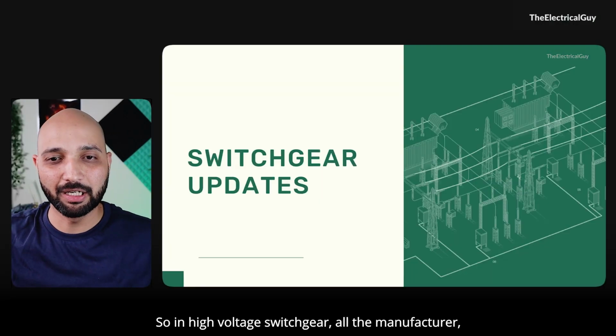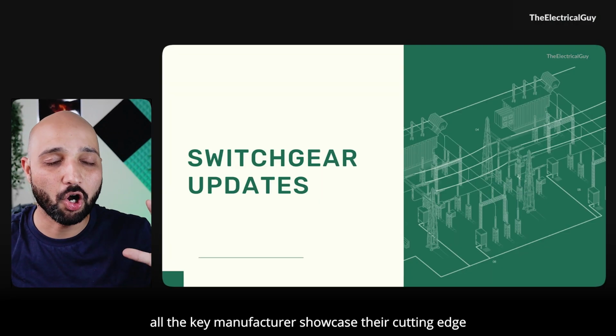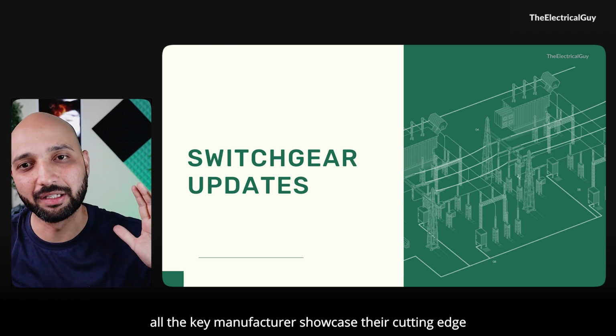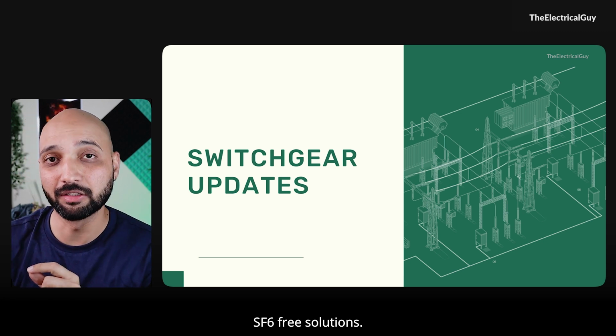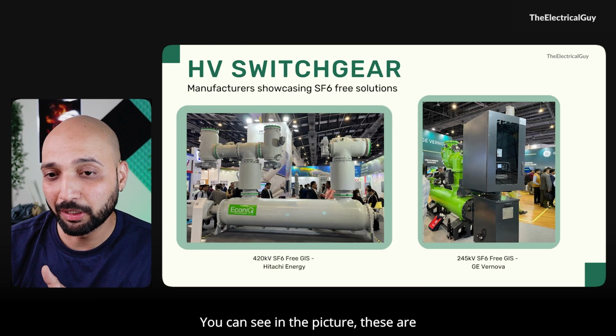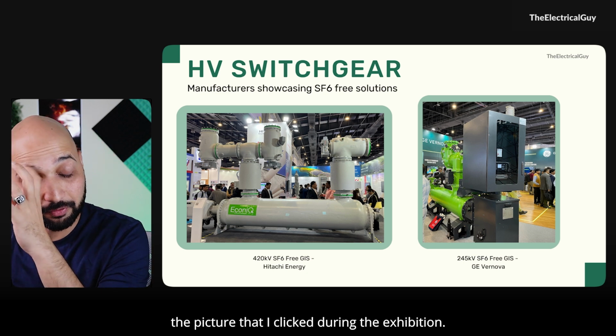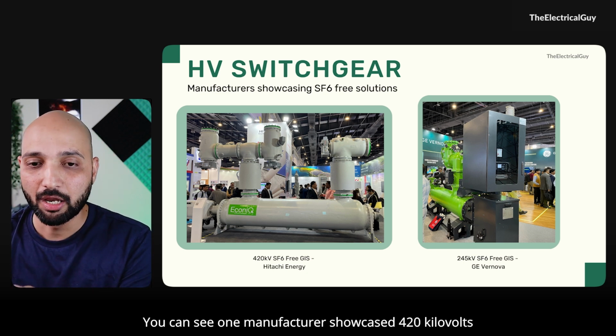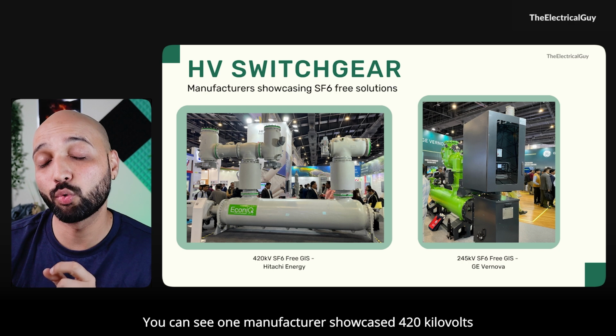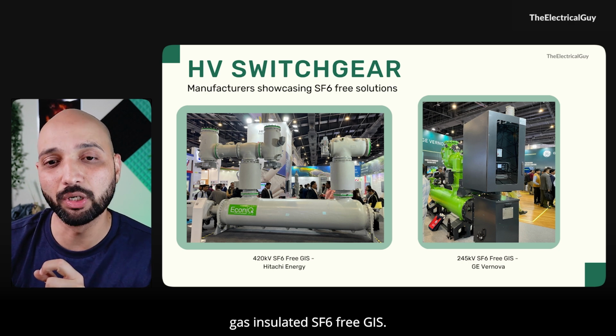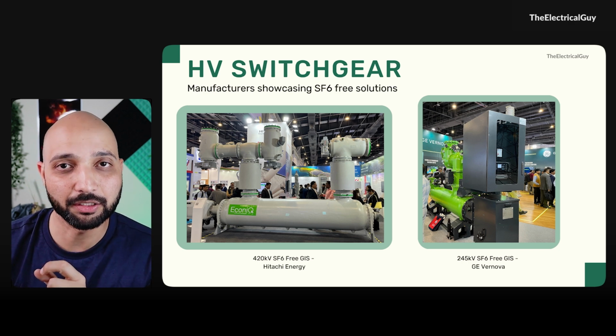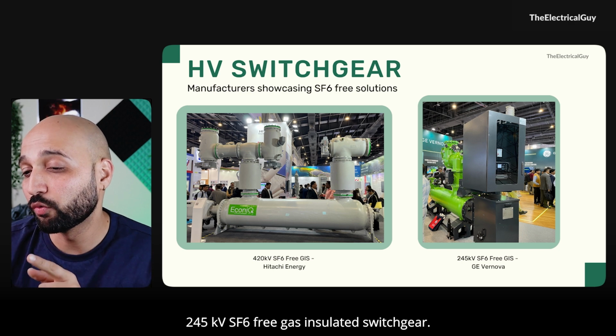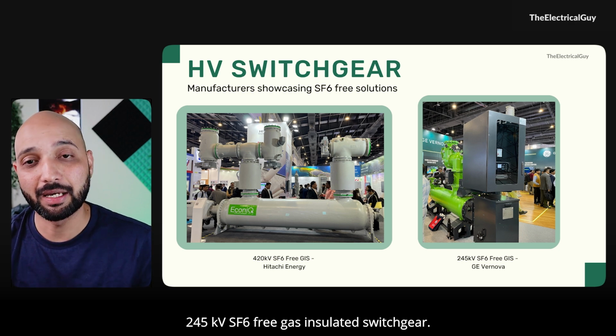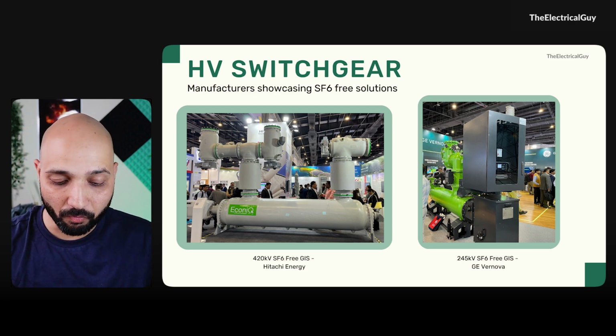So this time the switchgear focus was on sustainability, avoiding SF6 gas. In high voltage switchgear, all the key manufacturers showcased their cutting edge SF6-free solutions. You can see in the pictures I clicked during the exhibition, one manufacturer showcased a 420 kilovolt gas insulated SF6-free GIS, and on the right you can see a 245 kV SF6-free gas insulated switchgear.